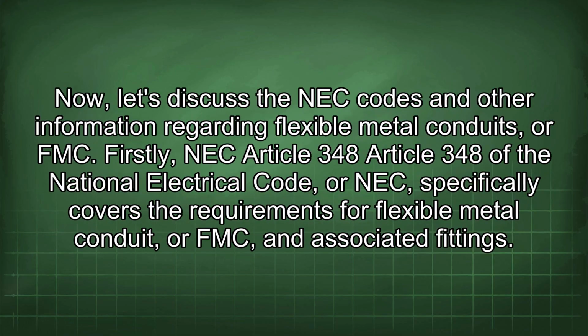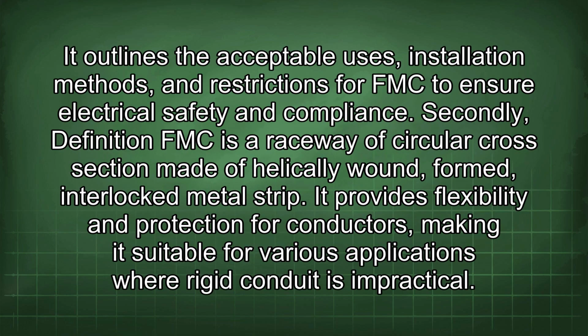Now, let's discuss the NEC codes and other information regarding flexible metal conduits, or FMC. Firstly, NEC Article 348. Article 348 of the National Electrical Code, or NEC, specifically covers the requirements for flexible metal conduit, or FMC, and associated fittings. It outlines the acceptable uses, installation methods, and restrictions for FMC to ensure electrical safety and compliance. Secondly, definition: FMC is a raceway of circular cross-section made of helically wound-formed, interlocked metal strip. It provides flexibility and protection for conductors, making it suitable for various applications where rigid conduit is impractical.